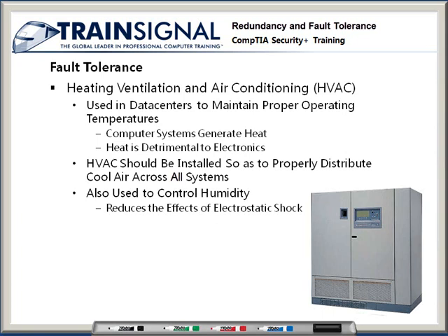Well, there are individuals that say between 40 and 55% humidity is perfect for a data center. And I agree that that's in a range that I'm comfortable with as well. But there are other camps that believe that the range should be between 20% and 80%. Now, in my opinion, the 40 to 55 feels better, but that's a pretty narrow range that you're playing with.